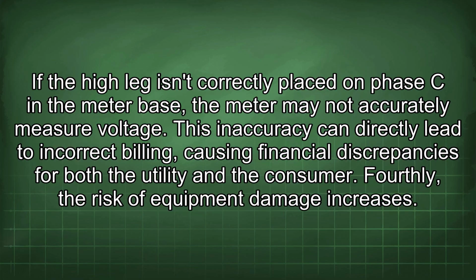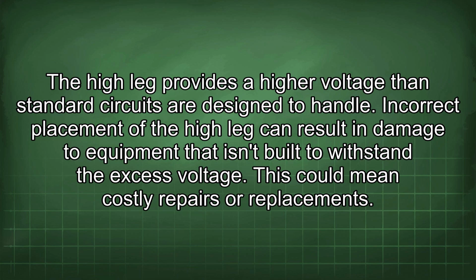Fourthly, the risk of equipment damage increases. The high leg provides a higher voltage than standard circuits are designed to handle. Incorrect placement of the high leg can result in damage to equipment that isn't built to withstand the excess voltage. This could mean costly repairs or replacements.